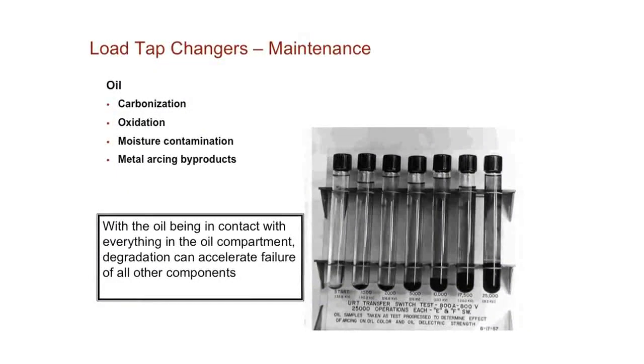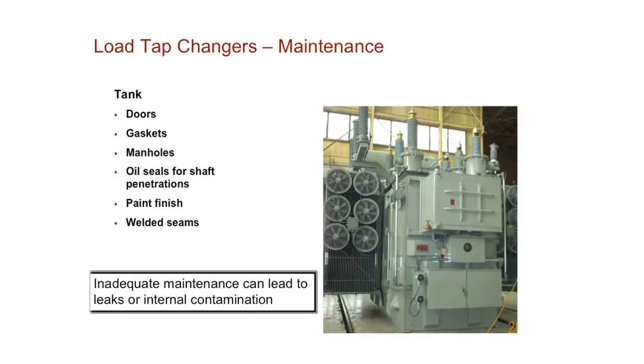Some other general maintenance, you're going to have oil handling. All these tap changers have oil in them, whether it's an in-tank tap changer or a tap changer on the end of a transformer. They're going to have oil of some form in them. Also, the visual inspection. When you're doing the visual inspection, you want to go inside. We'll talk about doing the tank inspection inside the unit, and we'll also talk about pulling the switch, the diverter switch, to look at the unit outside the tank as well.